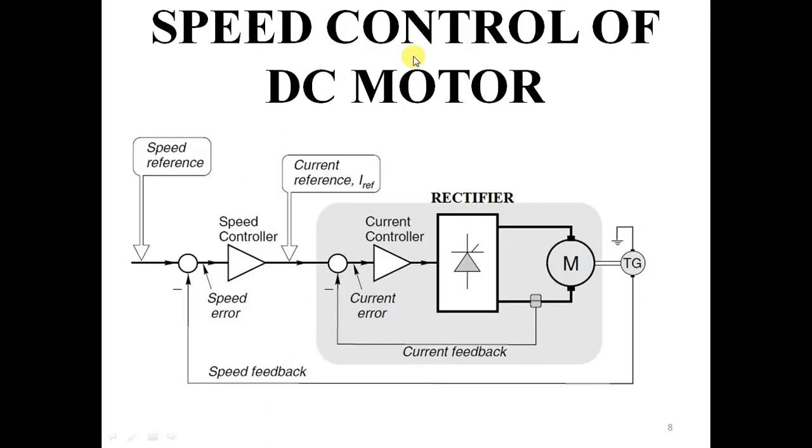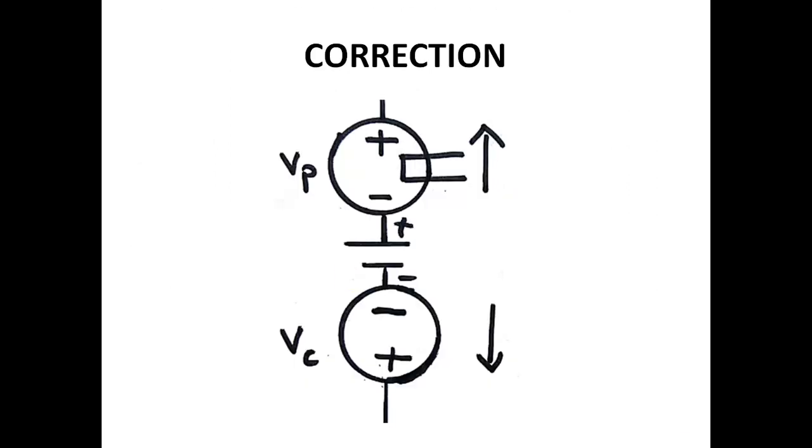This is closed loop control of DC motor. You have a speed loop which maintains actual speed is equal to set speed. You have a current loop which gives protection to the rectifier and motor. Whatever correction you do, that correction must be opposite to the disturbance. If disturbance is applied in this direction, the current must be in the opposite direction.